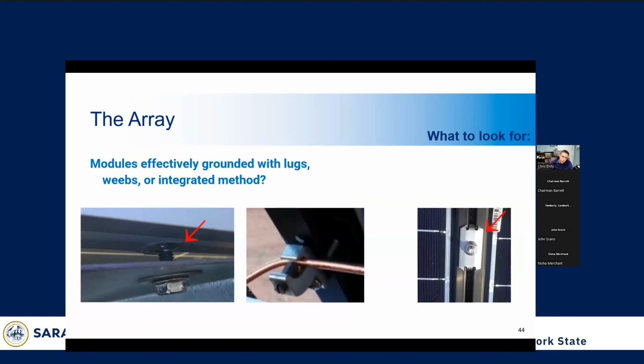Another thing that you want to look for when you're looking at the array is the grounding of the array. I doubt I need to tell anyone on this call that grounding and bonding of the array is not just a code issue, but also a safety issue. The integrity of the grounding system is vital to any electrical installation, not just PV. And in a PV system, it's dependent not only on the conductors, but also on the equipment itself, which is used to carry the fault current to an overcurrent protection device or a fault detection system. So in the event that there's a breakdown anywhere along the ground fault path, the fault won't be detected, which can leave conductive parts of the system energized, and that can present a significant shock hazard.